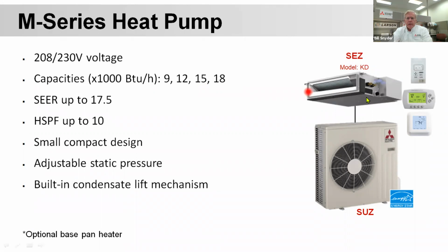This is an SEZ air handler. The SEZ air handler is a very, very low silhouette, probably about 8 inches tall, so it will easily mount in a small area. Some hotels mount them right above the little hallway into the space. They put it above the ceiling, so they'll drop the ceiling down 8, 9, 10 inches and put this unit in there. And then they just put a grill on here and blow it out into the room and put a return grill in the bottom. This unit here is designed for that type of application.